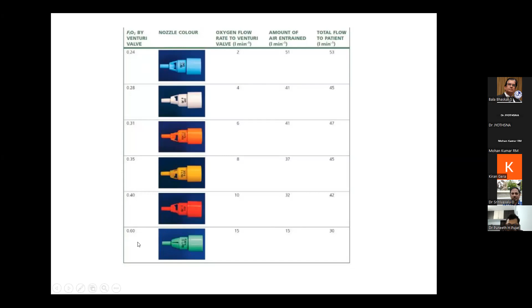The air oxygen ratio can be calculated with the formula 100 minus FiO2 divided by FiO2 minus 21. So at an FiO2 of 40%, the air oxygen ratio will be 3.2. So when the flow meter is set at 10 liters per minute, multiplied with 3.2, that is the amount of air entrained, we get 32 liters per minute.